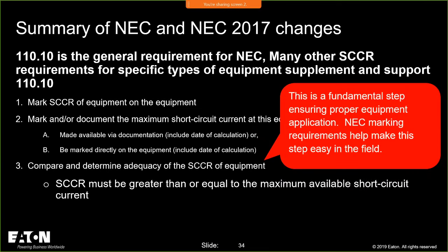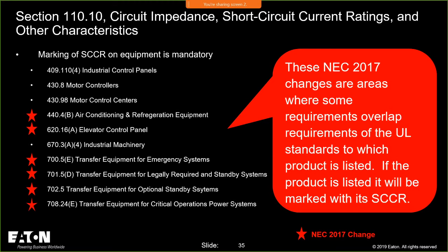And then remember that that comparison has to be made, and hopefully will be made, by your authority having jurisdiction or possibly the installers. Now, this is everywhere in the NEC where we have a marking requirement for short circuit current rating. And I think I'm going to go back to 408 because I may have missed a section in here. Let's take a look at what 408 tells us. In 408.6, I'm opening the book, I believe that whole section is new. Yes, it is. That whole section is new.